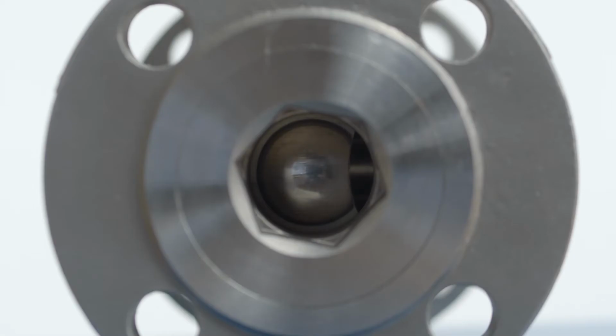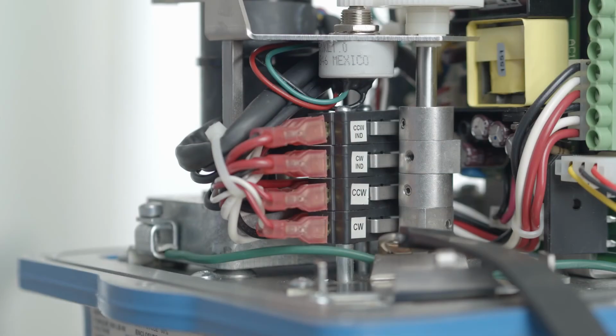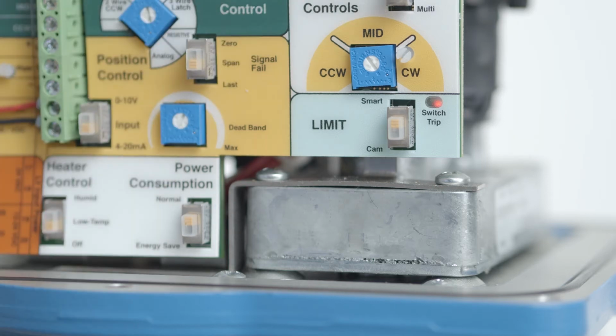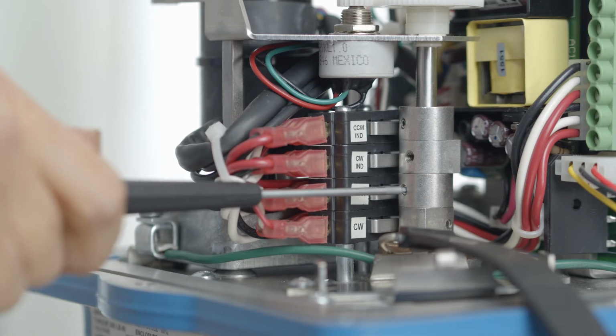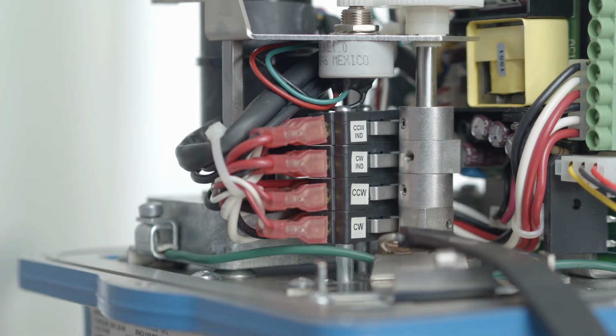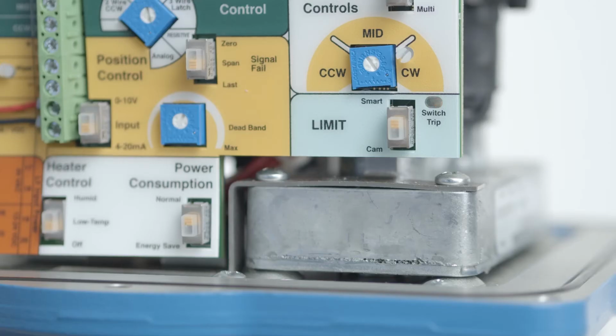Drive the actuator to the desired counterclockwise position using the CW or CCW push button. If the stall LED begins to flash, check to see if the limit switch cam is preventing the actuator from reaching the desired span end of travel, at which point the switch trip LED will be illuminated. If necessary, back the cam off so that it will trip the switch slightly beyond the desired end of travel and the switch trip LED will go out.